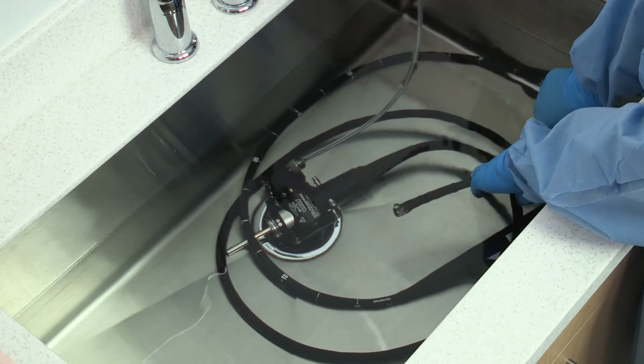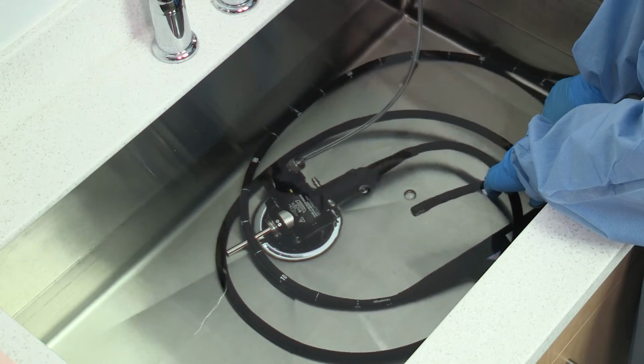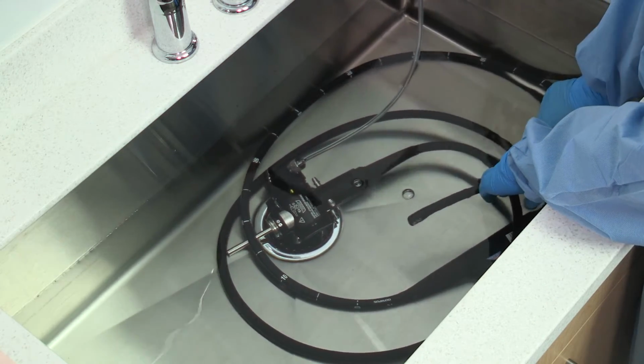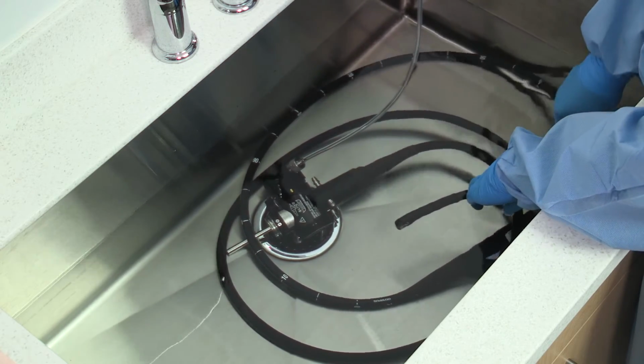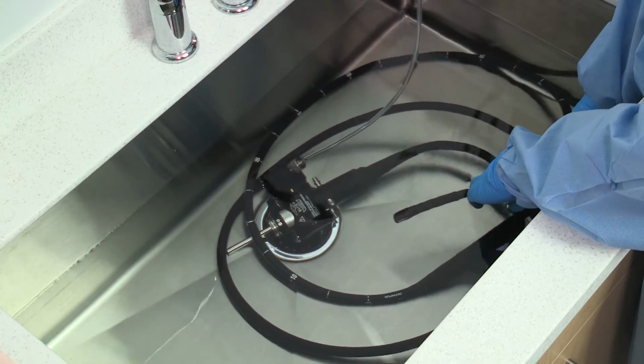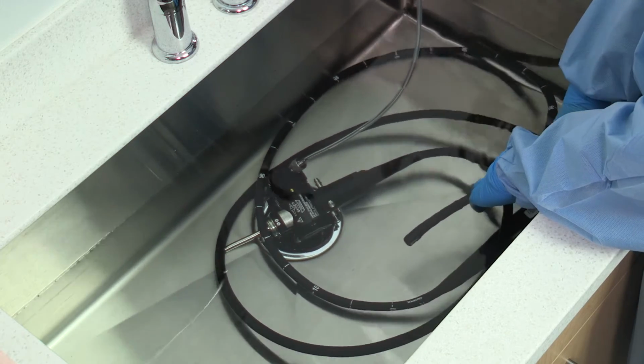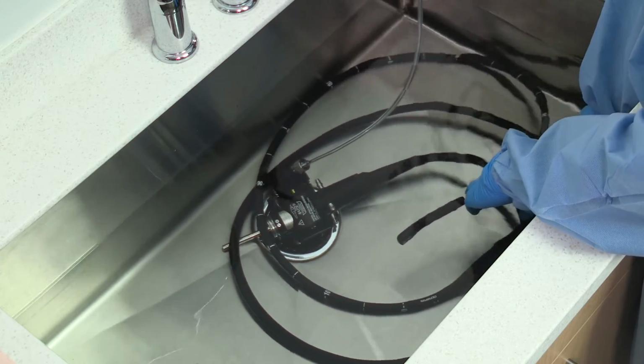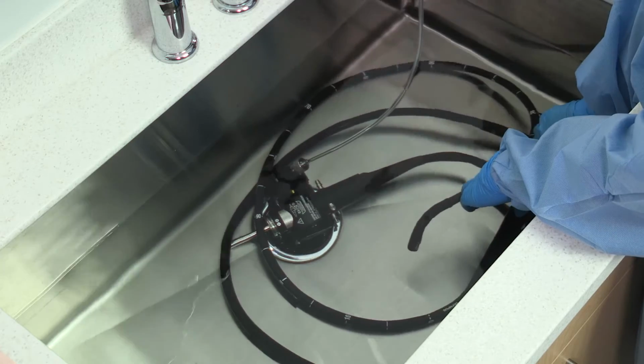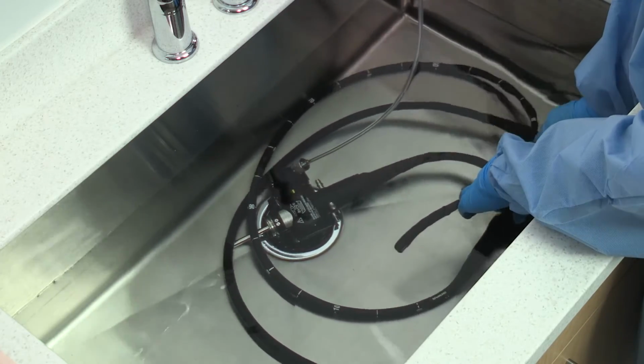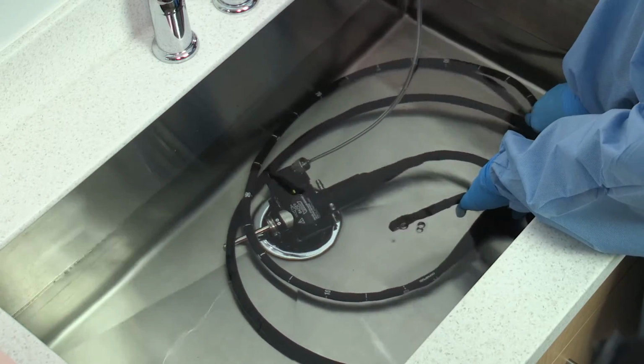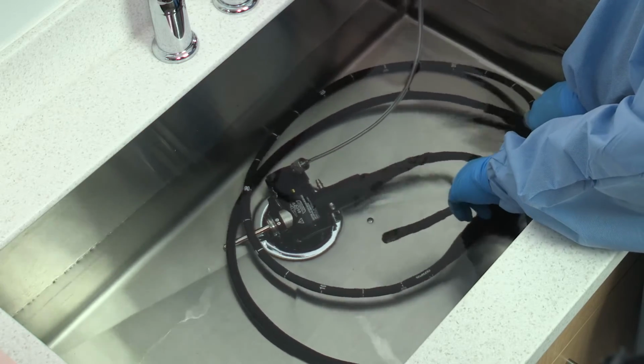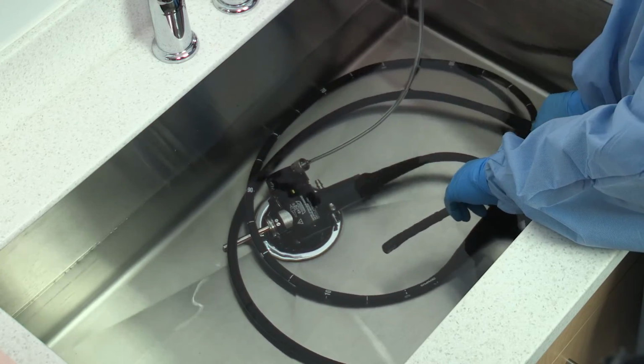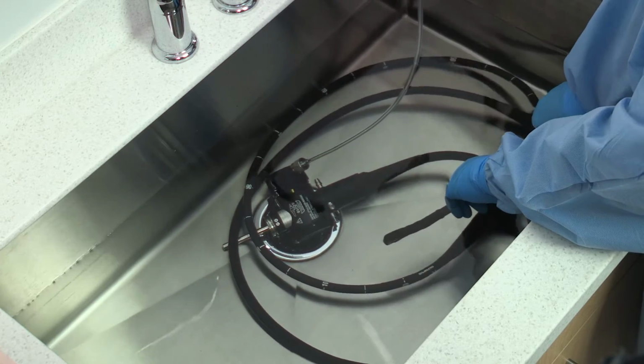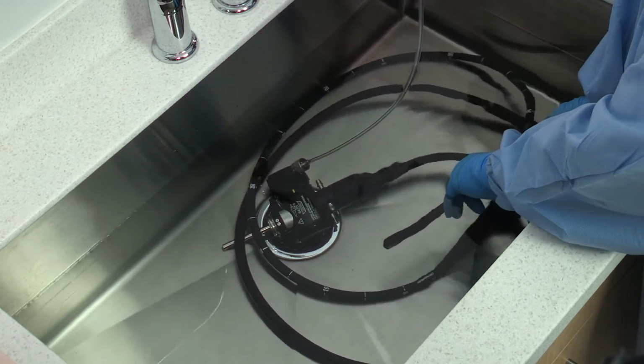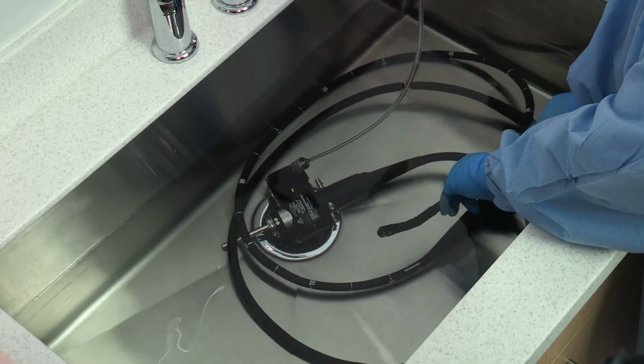Prior to the VERISCAN Leak Tester, leak detection has always been hampered by testing equipment that lacked precision and required extraordinary skills of observation beyond the capabilities of even the most experienced cleaning technician. As a result, undetected leaks allow moisture to enter the endoscope's interior through no fault of the technician. These leaks invariably result in extensive endoscope damage, expensive endoscope repairs, and raise the risk of cross-patient infection due to pathogens passing into subsequent patients through undetected leaks and moisture invasion.